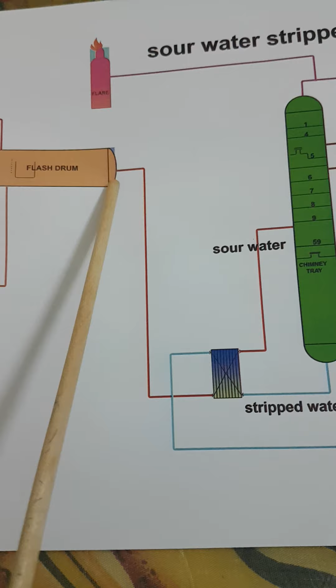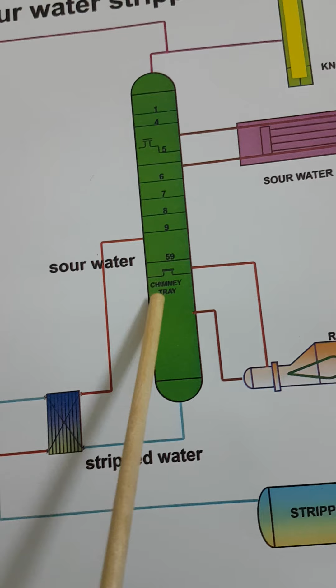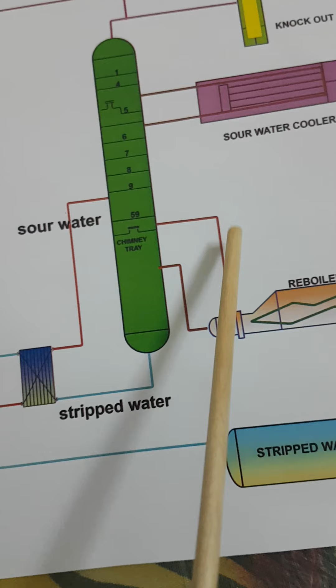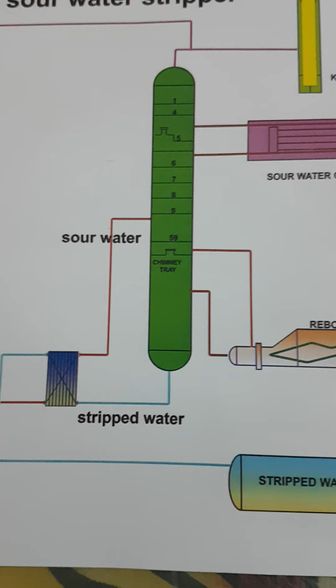There is no temperature control over here, but we maintain temperature in the stripper. I will explain how we maintain the temperature. We know that we have to maintain high temperature in the stripper, so we preheat the sour water in the interchanger. The preheated sour water will go to the feed tray and come here. Now you are going to learn how we maintain temperature. With the help of the reboiler, we raise the temperature, so temperature rises continuously. Now we have to maintain the temperature in an accurate and specific way, because if the temperature is too high, then hydrogen sulfide gas will get separated more, and there will be a continuous and huge supply and a huge pressure buildup in the sulfur recovery unit.